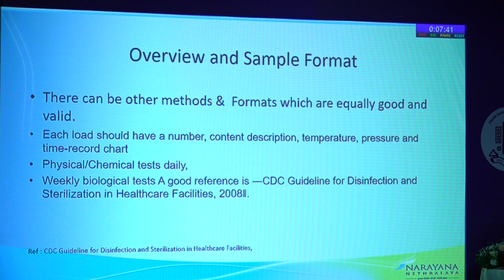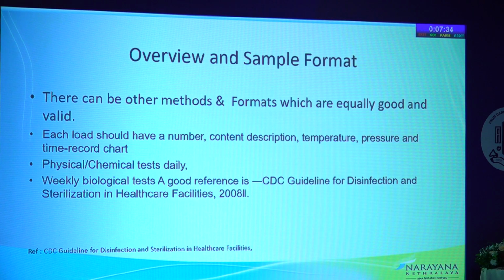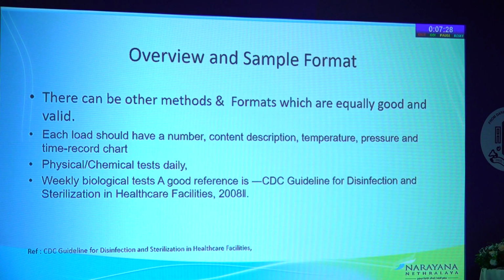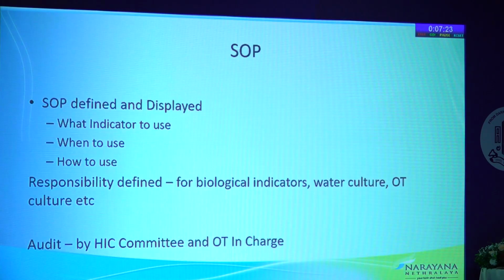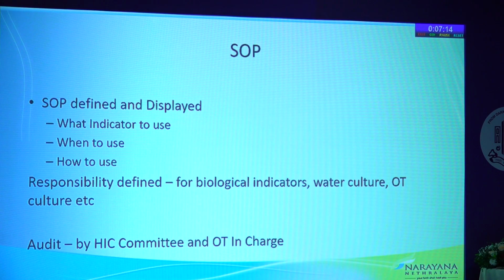Over documentation does not ensure results. And as far as CSSD goes, my personal view is that the CSSD staff will also change, and there will be multiple staff for us. If you simplify things to a 5th grade level, they work. If you complicate things with our knowledge, make them medical, they don't work. So to simplify that, what we have done is we have an SOP which says step by step how a machine is to be run. And the entire CSSD process, from washing, cleaning, storage, everything is in not more than 20 points. It's like 1 or 2 pages stuck there.